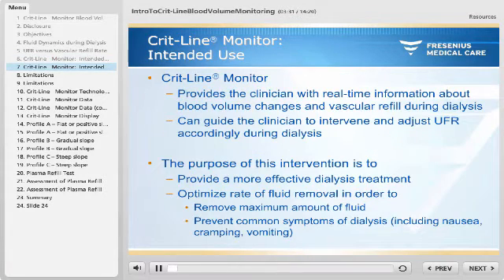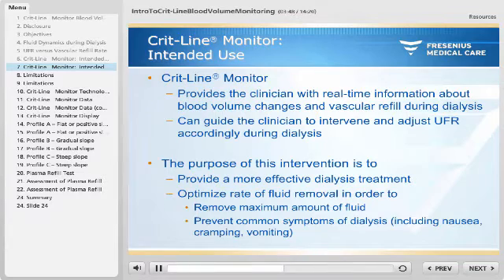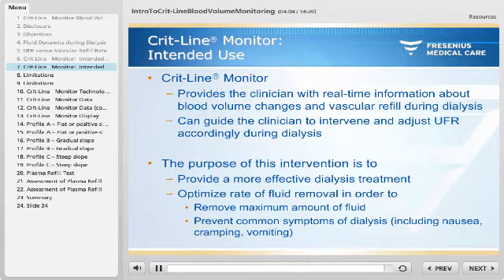The CRITLINE monitor provides the clinician with real-time information about blood volume changes and vascular refill during dialysis, and can thus guide the clinician to intervene and adjust the ultrafiltration rate accordingly. The purpose of this intervention is to provide a more effective dialysis treatment — to optimize the rate of fluid removal in order to remove the maximum amount of fluid, while also preventing common symptoms of dialysis including nausea, cramping, and vomiting.